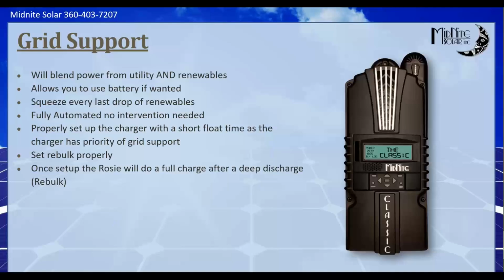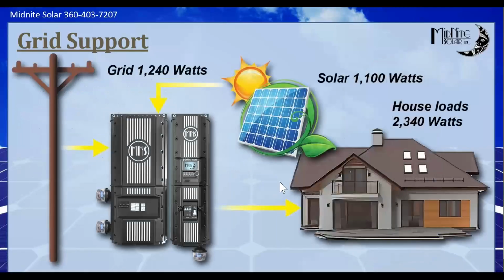The other nuance of grid support is that you will have that 150 to 200 watts coming from the grid to power your first 150 to 200 watts of load. Then it will prioritize the PV after that. Here's one of my poor examples of how this works, because my grid power up here really should be over by the pole. But in this example, the house is pulling about 2,340 watts. There's about 1,100 watts of solar available. It's going to pull the remaining 1,240 from the utility grid and blend it to power those loads, versus disconnecting from the grid or powering it all.